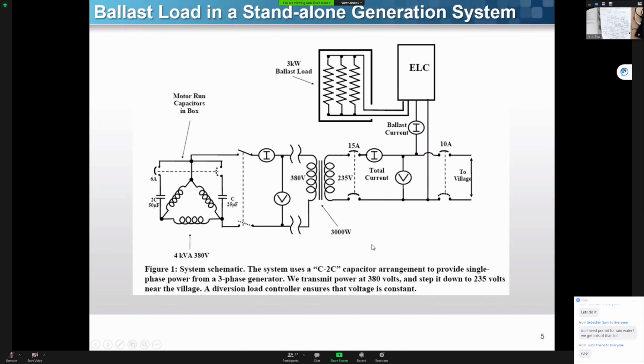So here the example shows you, they're using a three-phase motor, basically a squirrel cage induction motor, and they turn it into a generator. Because a three-phase machine might be easy to find and is smaller in size, but the power required down here is single-phase power. So they will have some type of converter to convert the three-phase power into single phase. Then they put the transformer to step the voltage down.